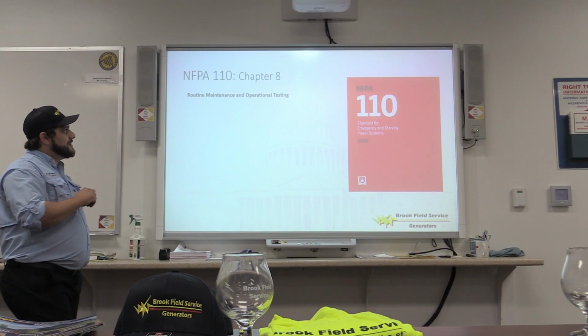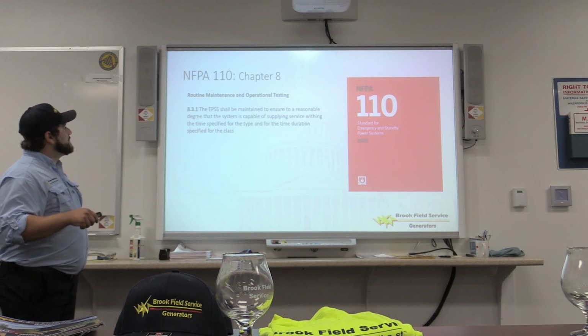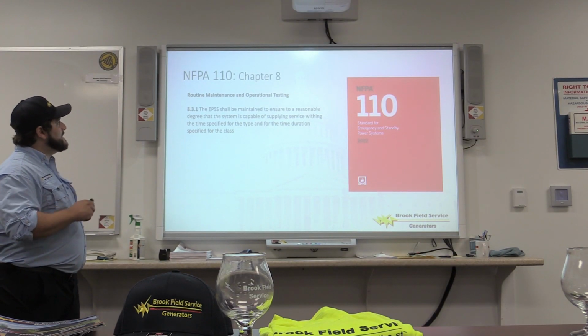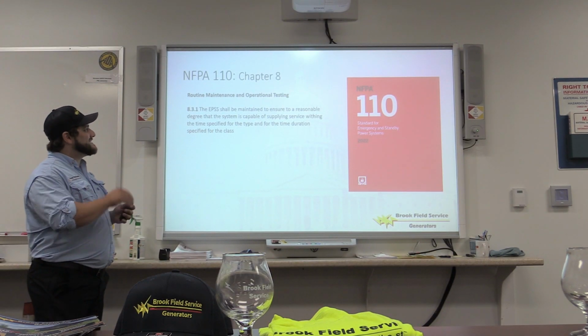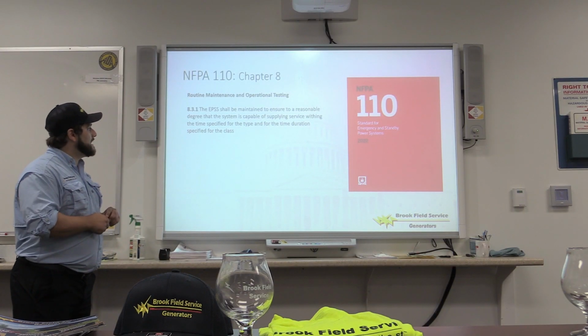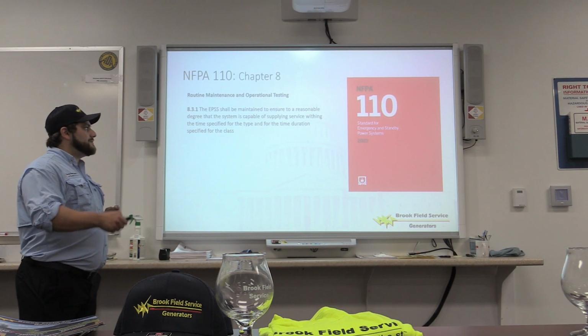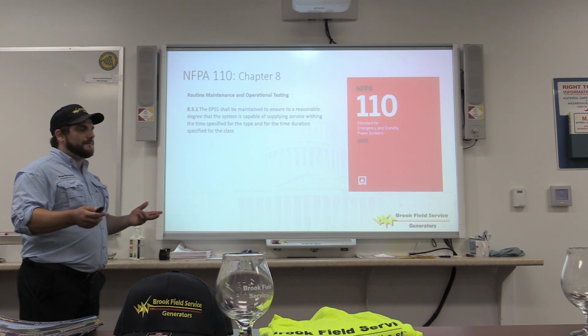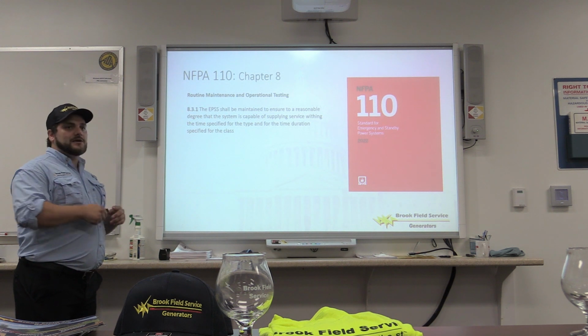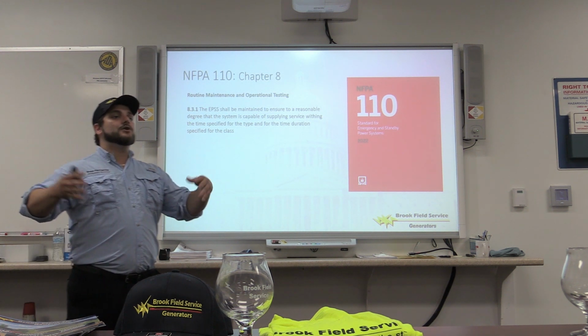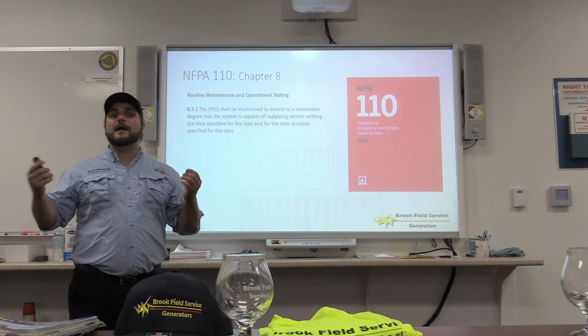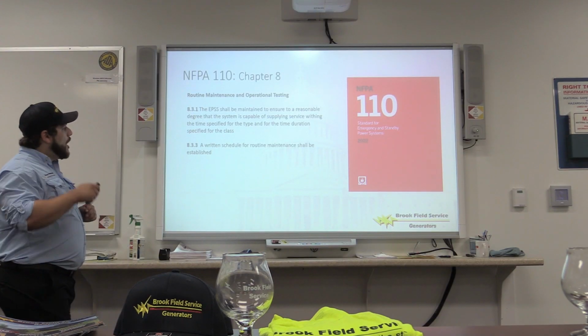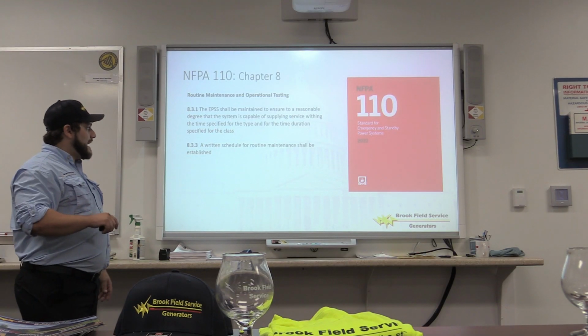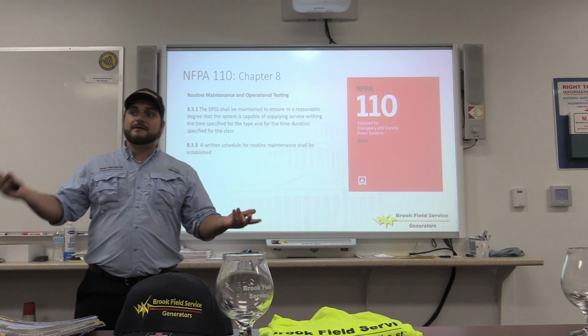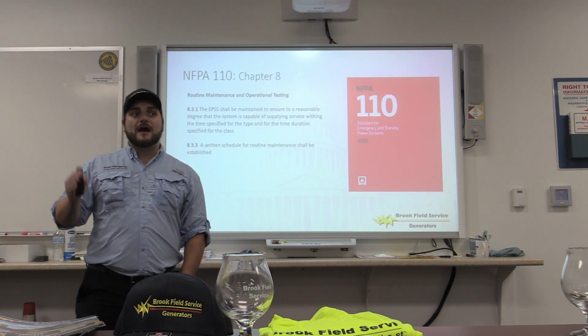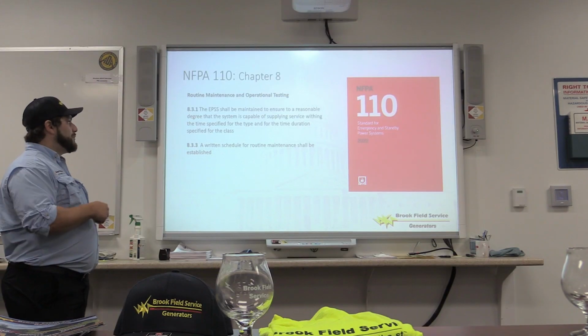Now, routine maintenance and operation testing is why we're all gathered here today. Section 3, subsection 1 says that the EPSS shall be maintained to ensure, to a reasonable degree, that the system is capable of supplying service within the time specified for the type and for the duration of the specified class. That translates back to Chapter 4, but again, it's making sure that when we go in and do our rating of your system, you have a system that is, to Ted's point, capable of supplying the power that it is rated to supply. A written schedule for routine maintenance will be established. Whether that's someone having it scheduled every 6 months, have it on paper, so when the inspector comes, you have the proof of that.